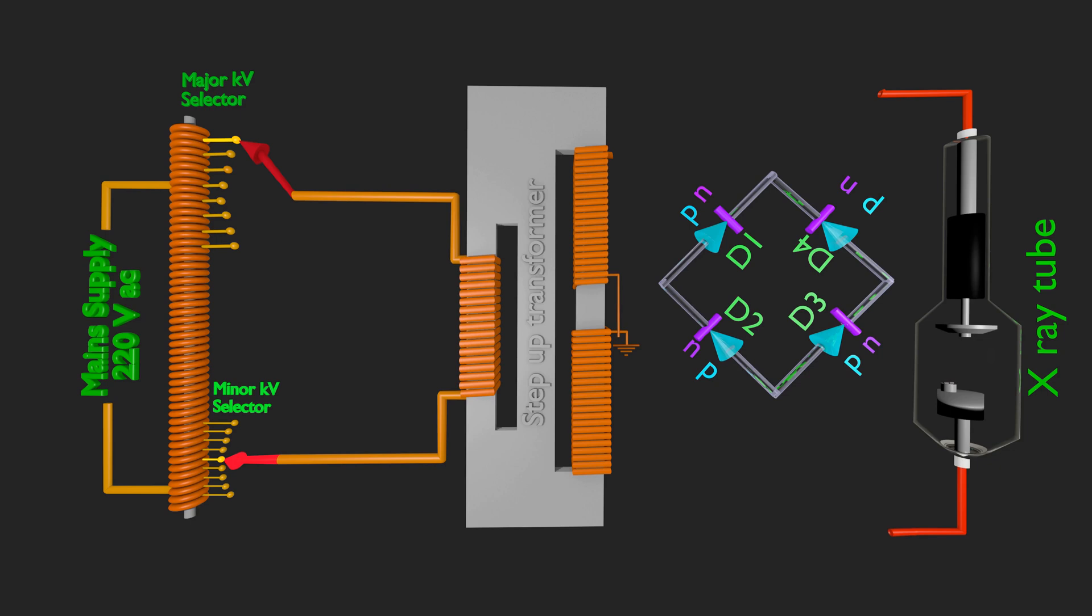A bridge rectifier shown here consists of 4 PN junction diodes D1, D2, D3, D4. Bridge rectifier takes input from secondary of step-up transformer. An X-ray tube is connected to the output of bridge rectifier.